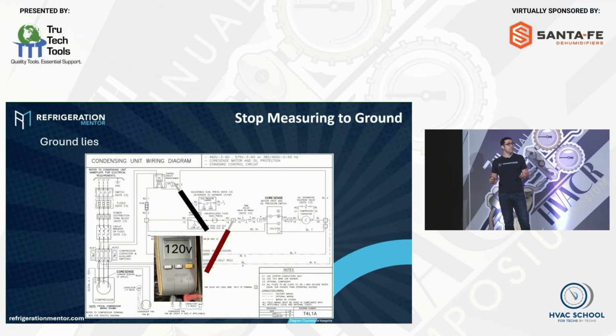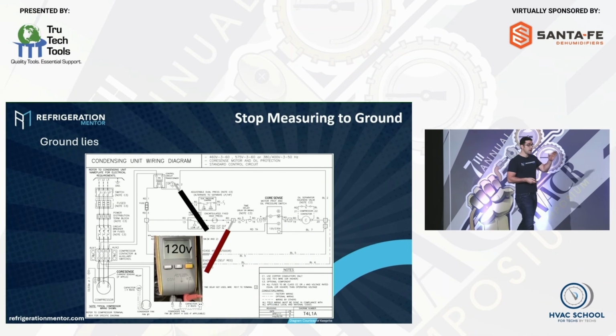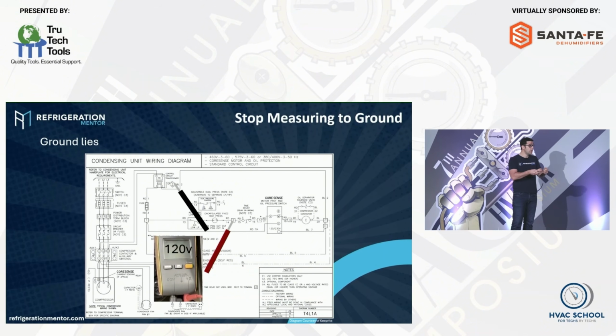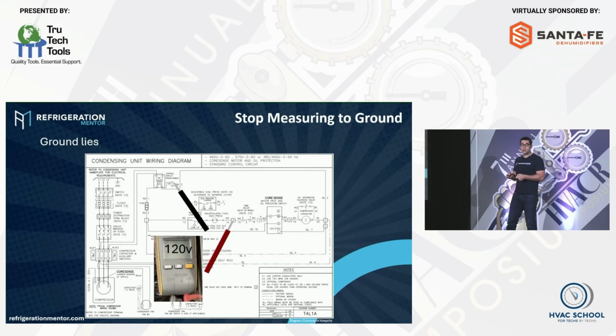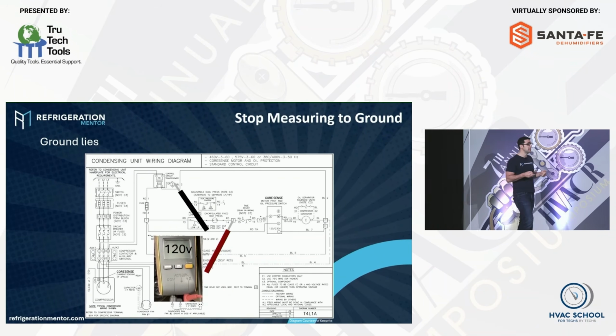What do we use ground for? We use ground to check for potential. That's safety. You shut off a breaker and you're going to put your hands on the wire. You want to make sure there's no power there so you don't get a shock. When you go to ground, it lies. It lies. And we'll talk about that and why does that lie.